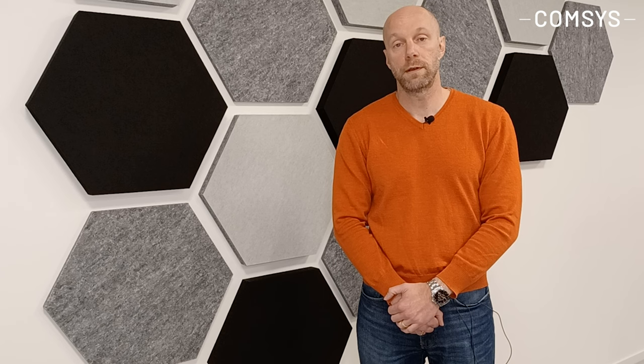The harmonic orders, if we have a three-phase load, will be the 5th, 7th, 11th, 13th, and so forth — the six-pulse harmonics, which are equivalent to 6n ± 1. So for 6×1 ± 1 we get five and seven, and for 6×2 ± 1 we get eleven and thirteen, and so forth.